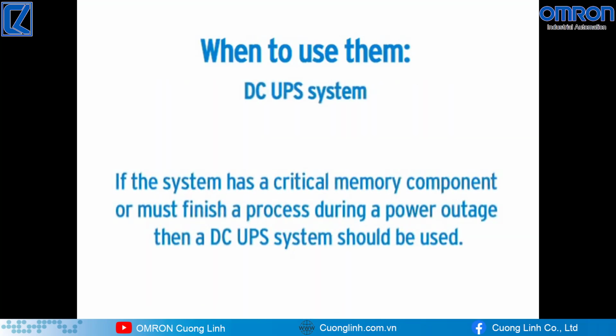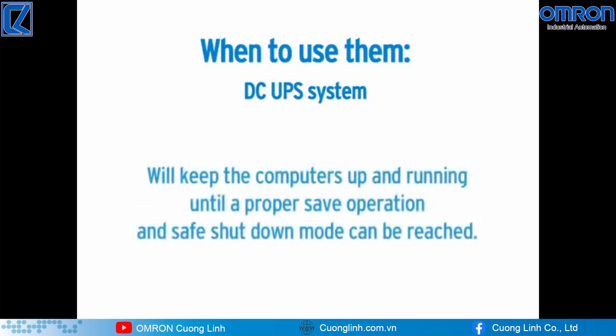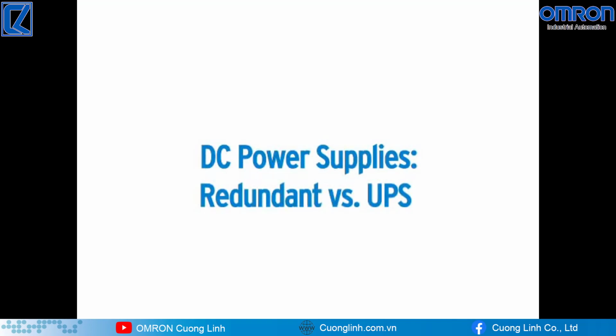If the system has a critical memory component or must finish a process during a power outage, then a DC UPS system should be used. The UPS system will keep the computers up and running until a proper save operation and safe shutdown mode can be reached. The cost will increase with the amount of equipment required for powering the UPS battery system. The two systems, redundant power supplies and DC UPS, do not offer a solution to the same industrial manufacturing concern. Carefully choosing the correct solution can help keep the manufacturing up and running and save money at the same time.